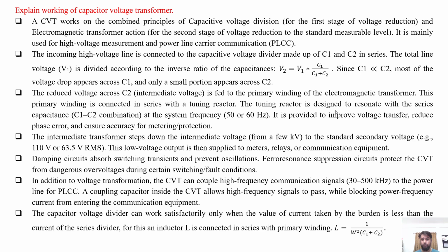few kilovolts value, and electromagnetic transformation action from the first stage output of few kilovolt voltage reduced at the intermediate level across the C2 capacitor, that is to be transformed with the help of the transformer to the secondary side of the potential transformer to a standard measurable value, that is 110 or 110 by root 3 value. It is mainly used for high voltage measurement and power line carrier communication for the communication purposes.